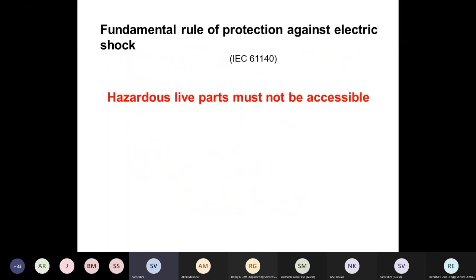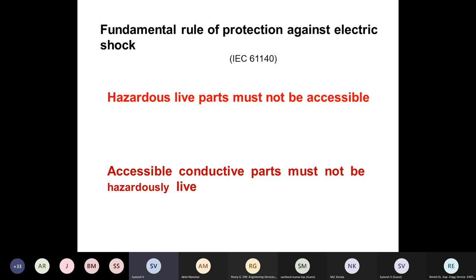Fundamental rules of protection against electric shock. There are two rules. Hazardous live parts must not be accessible. The second one is accessible conductive parts must not be hazardously live. So we will see these things. Hazardous live parts must not be accessible.